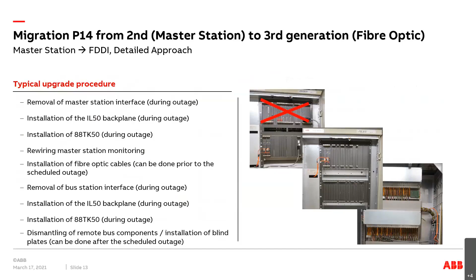During this upgrade procedure, you have to exchange components as shown here. You can already see that the overall quantity of components will be reduced. In the old configuration of the master bus station, a redundant installation uses 2 times the TK05 and FT05, as well as the bus termination modules FK05 and IL06. In the new redundant fiber optical configuration, you use only 2 redundant TK50 modules, plus the fiber optical cable that replaces the obsolete coax cable.